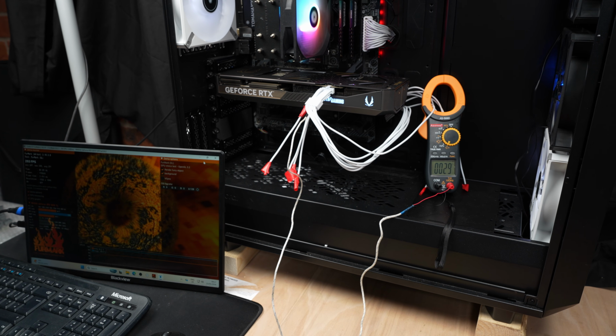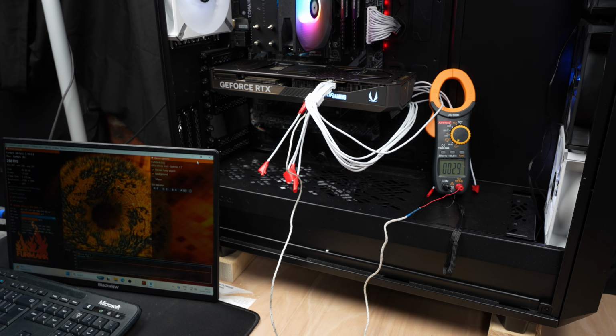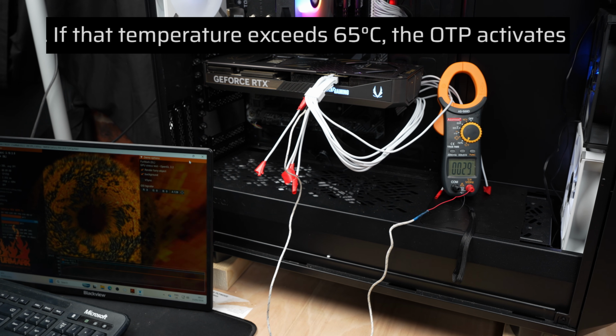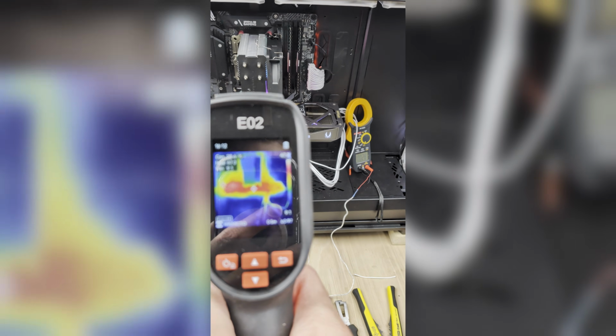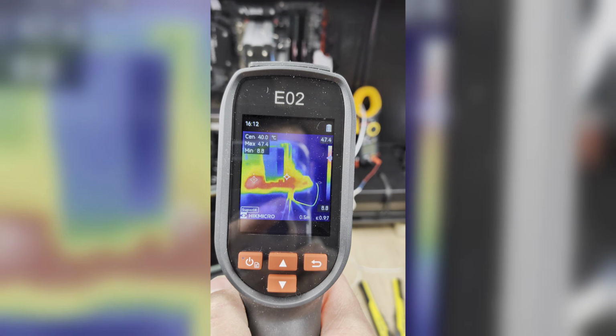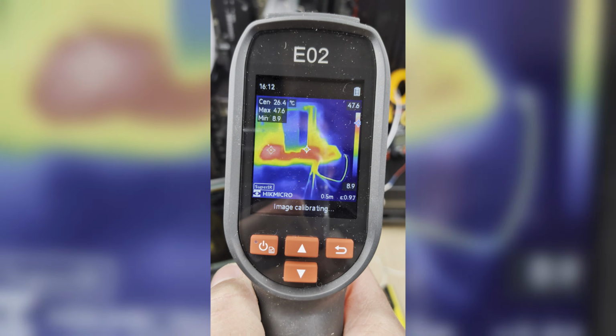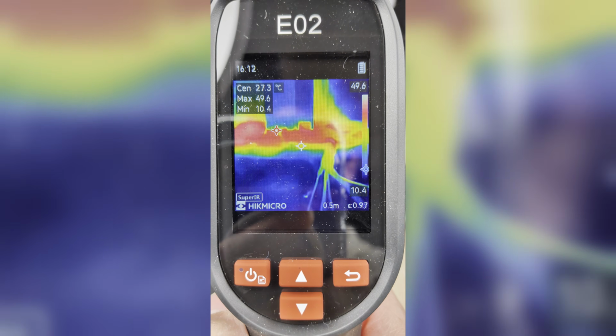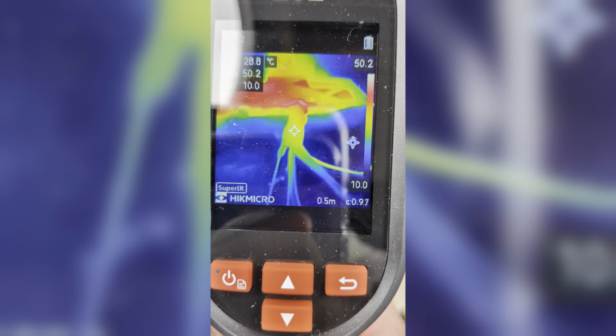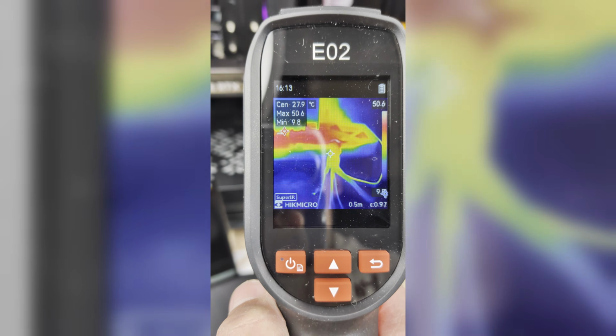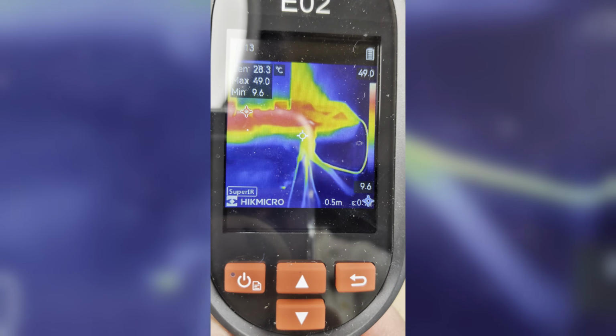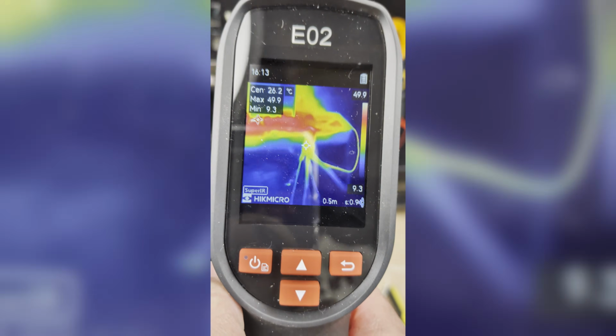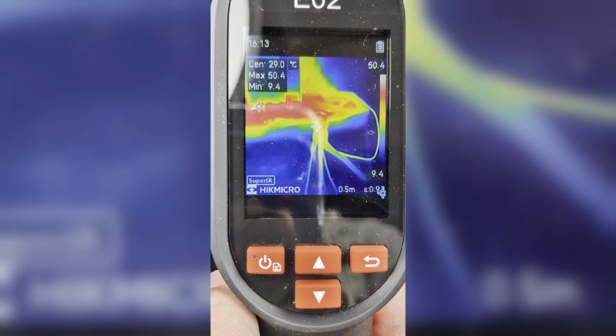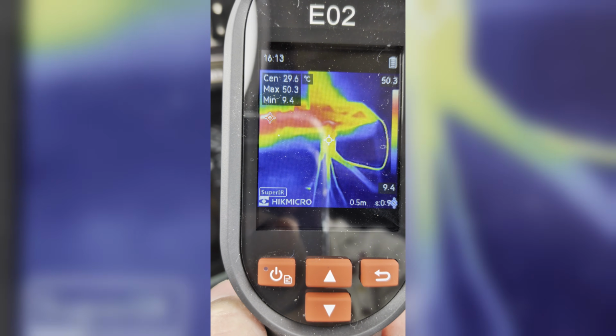I monitored the temperature of the probe, and even after 25 minutes it was barely getting above 30 degrees Celsius, which clearly isn't enough to trip the protection, set at 65 degrees Celsius. The thermal camera view backed this up too — one remaining individual wire stood out as hot, but the cable comb containing the temperature sensor was only hitting 25 to 30 degrees Celsius, far below the level needed to trip it.